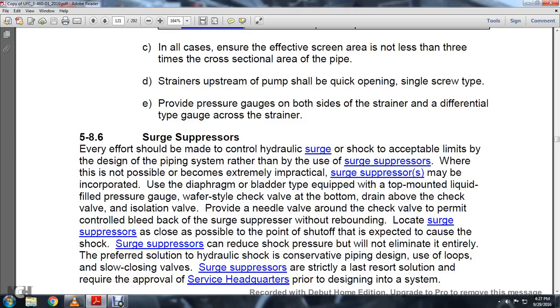5.8.6 Surge suppressor. Every effort should be made to control hydraulic surge to an acceptable limit through piping design, rather than use a surge suppressor. Where that is not possible or becomes extremely impractical, a surge suppressor may be incorporated. Use a diaphragm bladder type equipped with a top mounted liquid filled pressure gauge and a wafer style check valve at the bottom.